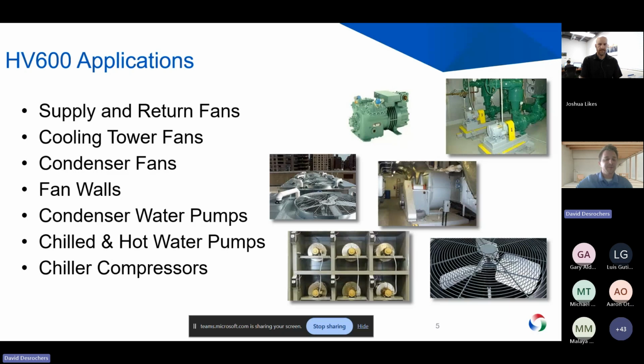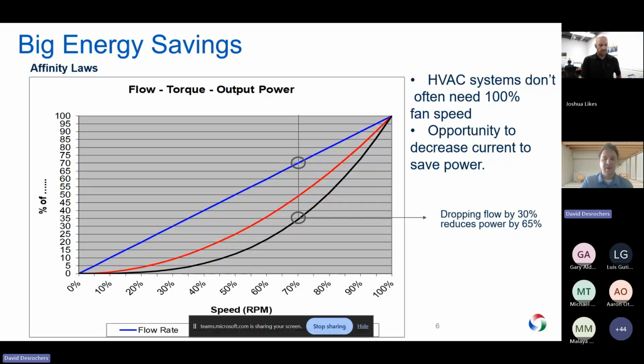Something to note on Yaskawa, at least, we only run 3-phase input motors. So if you have a single-phase motor, something real small, like maybe a kitchen exhaust fan that's 120 volts, single phase, that is not where we're going to shine. That's not the market that Yaskawa focuses on for VFDs. That might be better served by an SCR type dimmer switch kind of controller. Mainly, those big, larger fans for your facility and pumps is what we're going to be aiming at. So like I said, with energy savings, this breaks down to what we call the affinity laws.